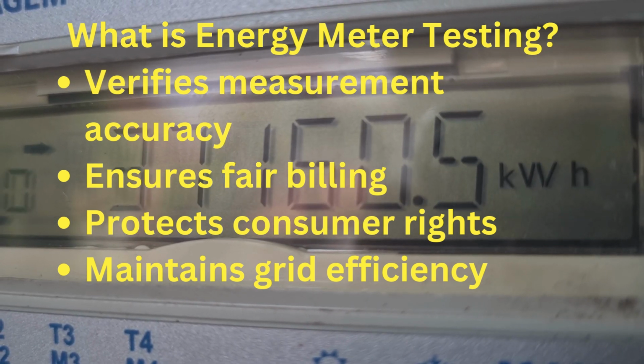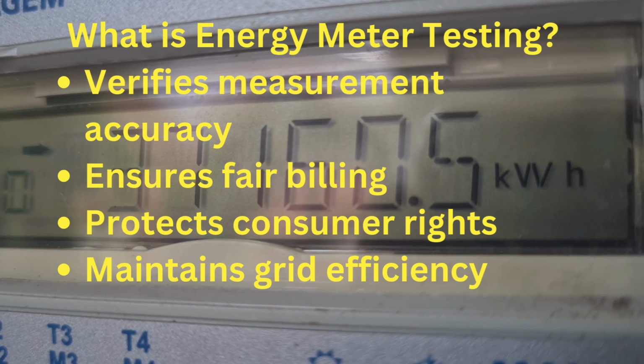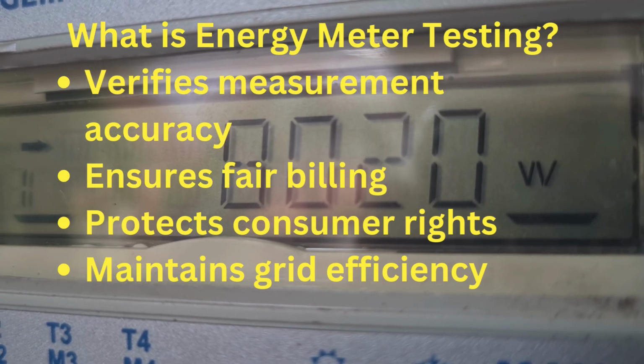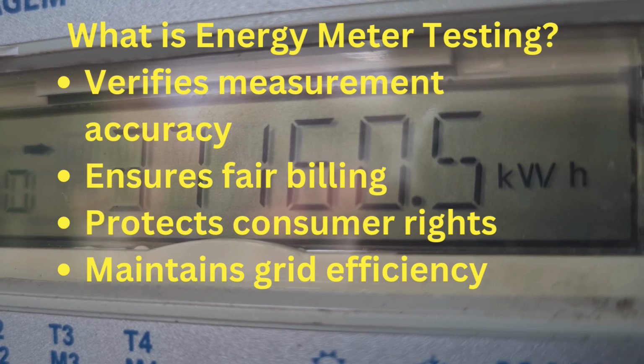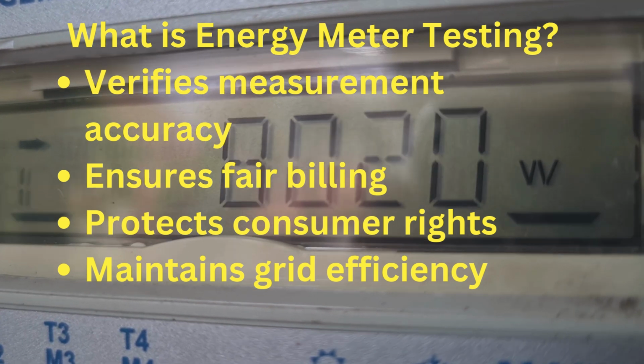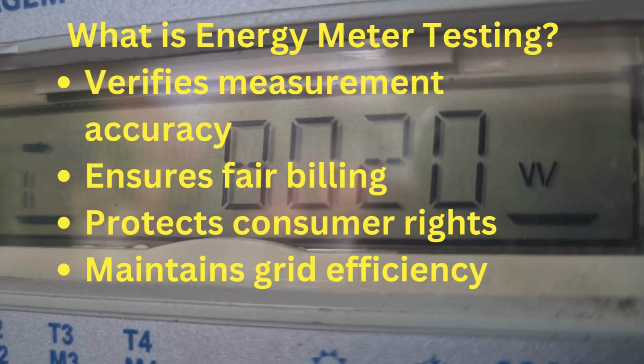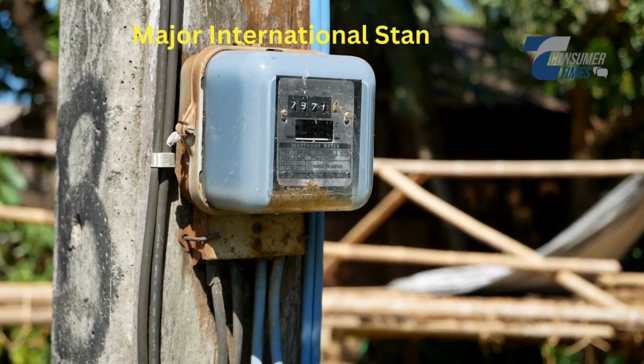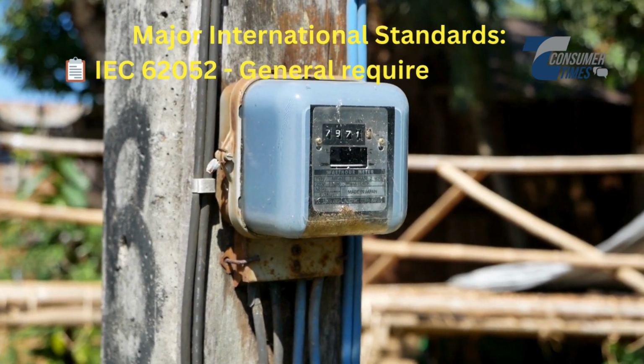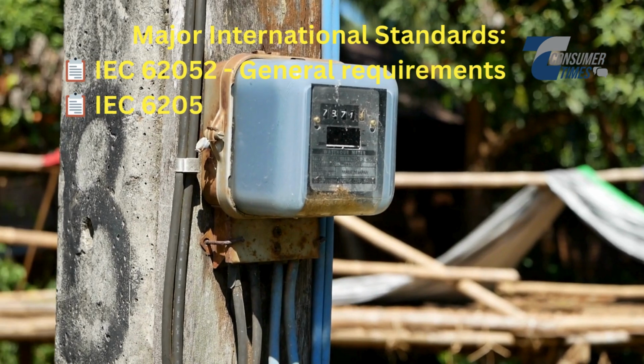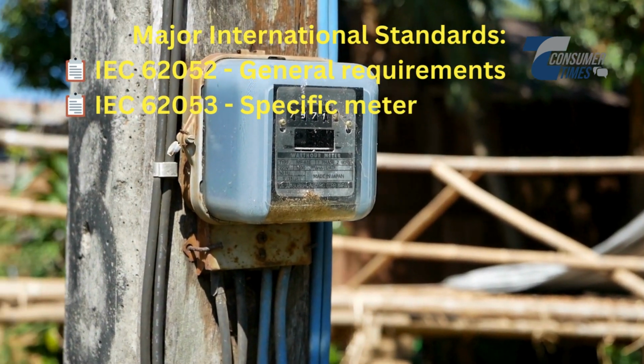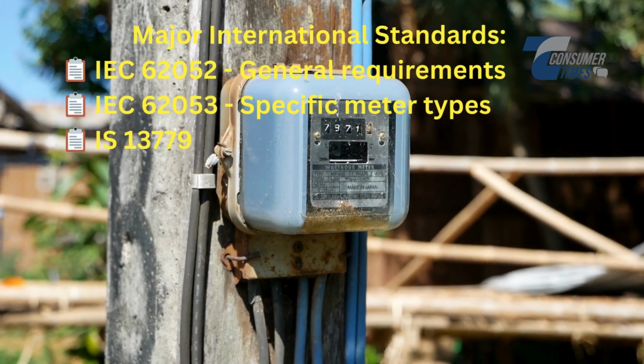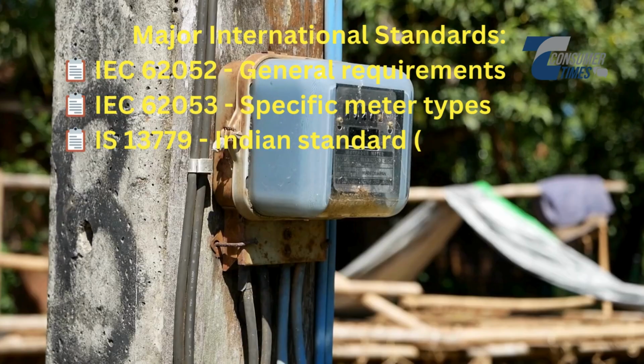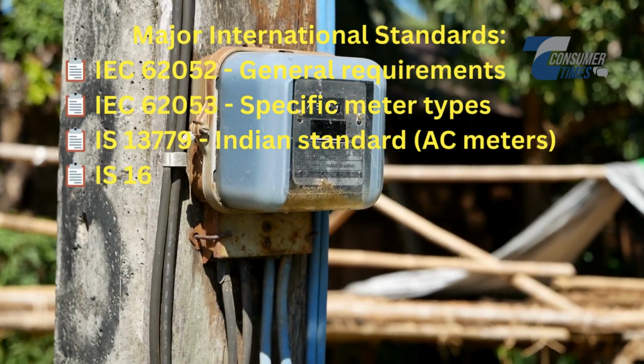Now imagine if this meter is inaccurate, you could be paying more than you actually consume, or in some cases, paying less, which creates issues for the power distribution system. This is exactly why energy meter testing and calibration are absolutely critical. Testing ensures that the meter is measuring accurately, while calibration is the process of adjusting the meter to meet specific accuracy standards. Without proper testing and calibration, you cannot trust the readings, and that's where international standards come into play.